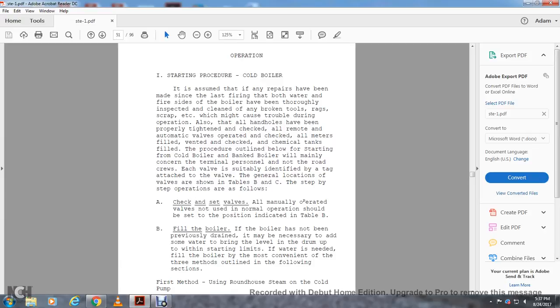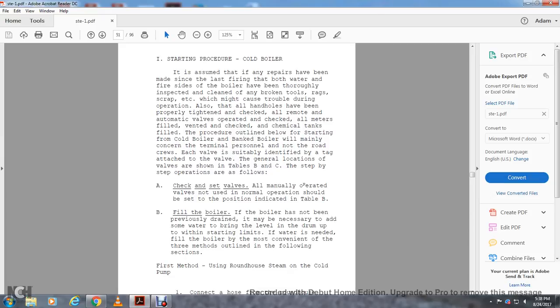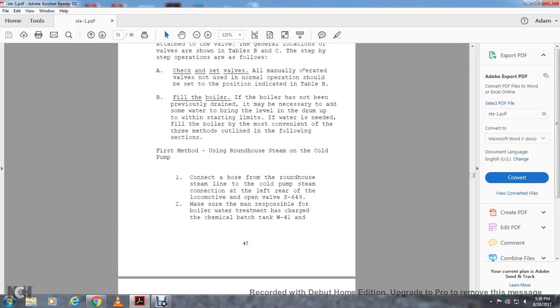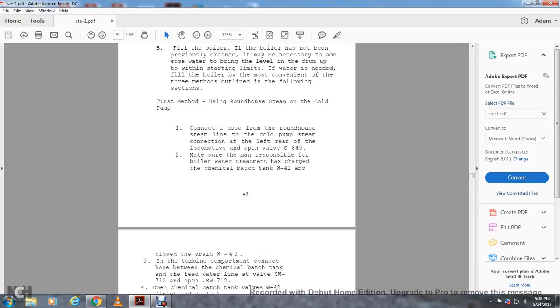Fill the boiler with water. If the boiler has not been previously drained, it may be necessary to add water to bring the level of the drum up within the starting limit of the water gauge. First method: using the roundhouse steam cold pump. Connect a hose from the roundhouse steam line to the cold pump steam connection at the left rear of the locomotive, opening valve S-649. Make sure the man responsible for boiler water treatment has charged the chemical batch tank W-41 and closed drain W-43.